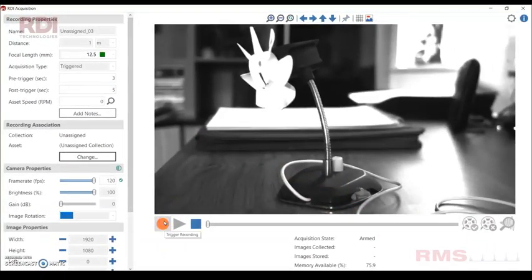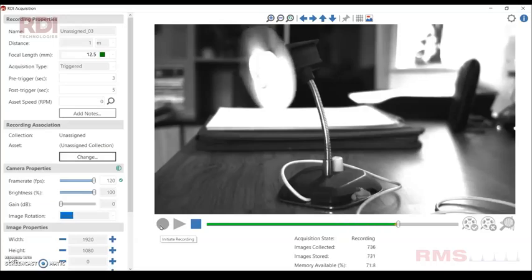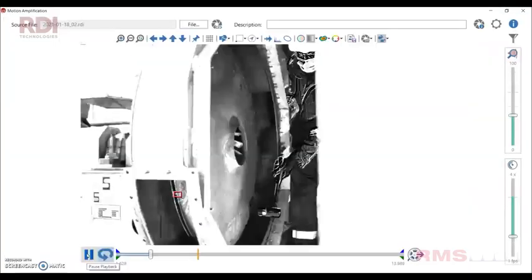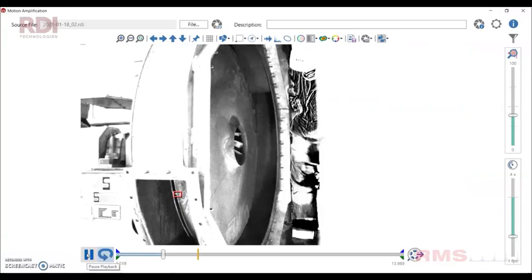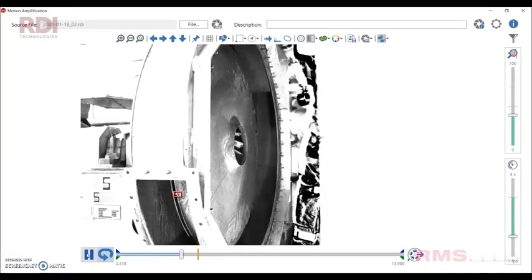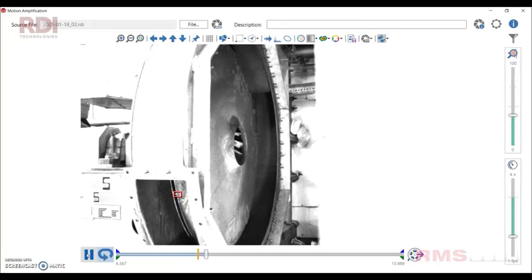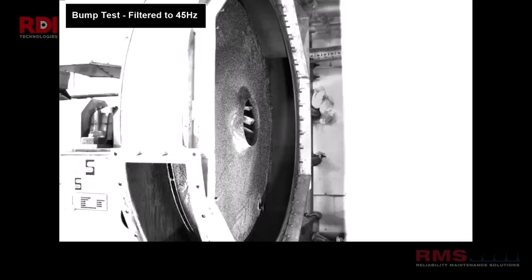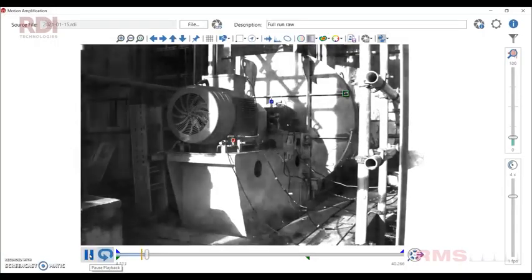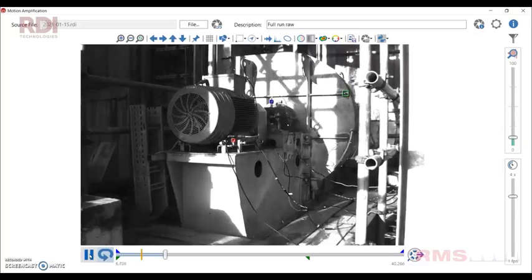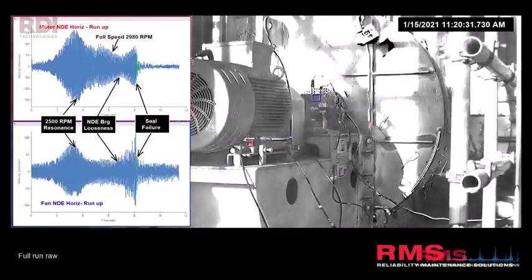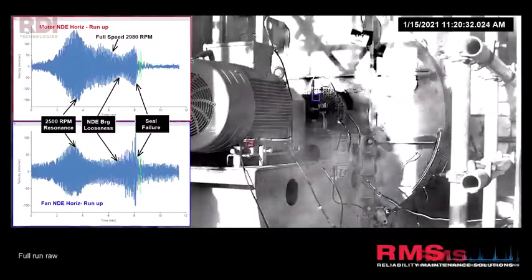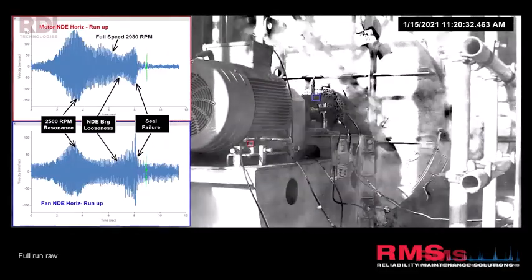We've got a little fan here, you arm the system, it starts to buffer and then it's live. We then see the machine start, press the icon and it's recorded the pre and post buffer. Fantastic tool, great for things like bump tests as we're seeing here. And then we can obviously isolate the individual frequencies. This is a filtered reading of a bump test. It's really great for capturing these transient events.